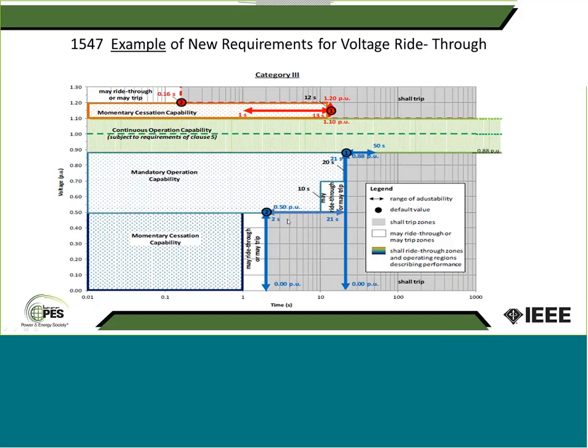Then if that requested setting is within this adjustable range, the DER still remains NRTL certified. So you're not violating the certification by changing those trip points. The ride-through itself is a capability. It's not a trip. So if you look at this figure here, the green area says do not trip.